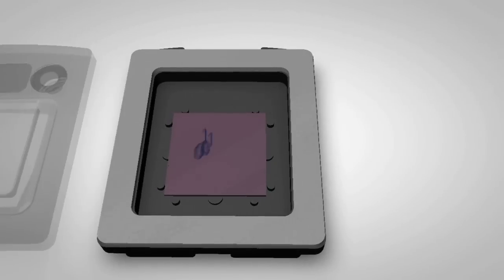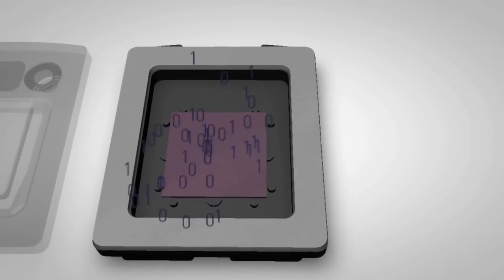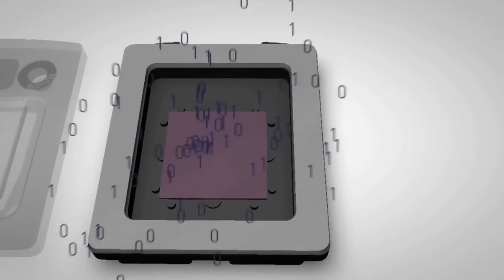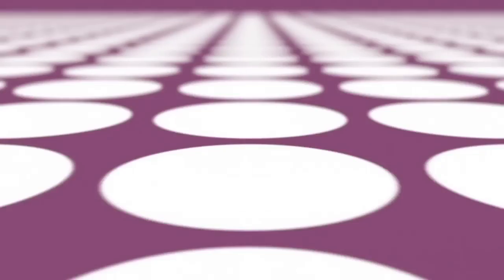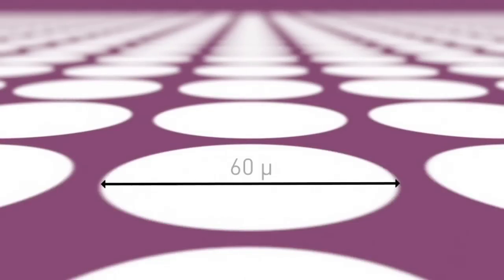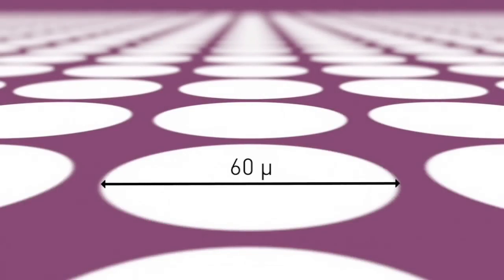At the heart of the QuantStudio 3D Digital PCR system is a new and high density PCR chip manufactured from a solid silicon substrate and etched with consistently sized nanoscale partitions. The chip enables 20,000 PCR reactions.